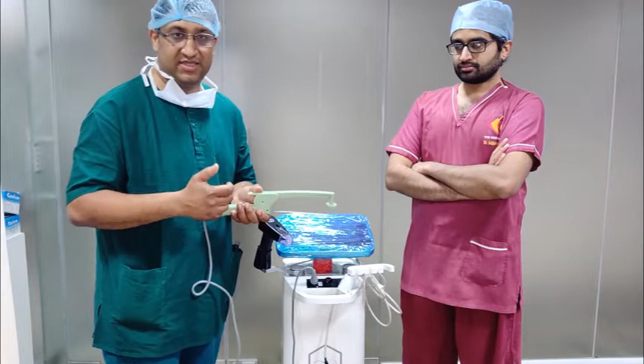Whenever we are using the device, the moment the temperature goes beyond that set temperature, the machine will stop its RF energy, and you just have to move to your plane, and then it will start. So in that way, you are never causing any burn to the body. So it is that safe. All right.